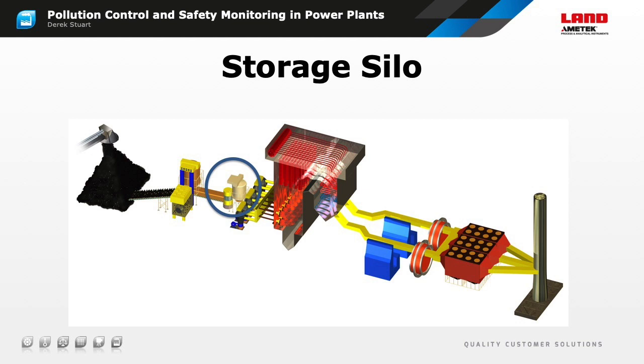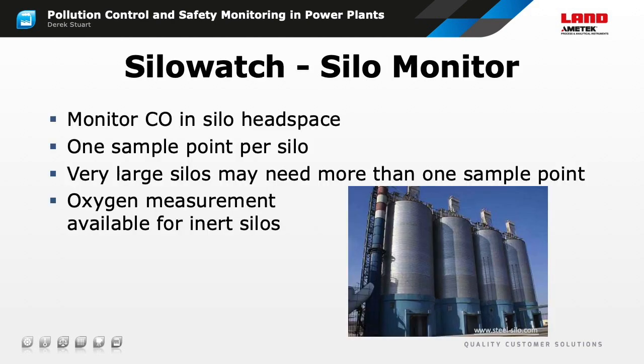Silos are used for short-term storage of fuel close to the boiler. They give protection from the weather and keep the fuel dry. Wet coal reduces combustion efficiency, but enclosed storage is essential for biomass pellets because they will simply disintegrate if they become wet. Because they're enclosed spaces, silos and storage domes are best monitored using a carbon monoxide sensor. The sample point should be located near the top of the silo so it can measure the gas in the headspace above the fuel. In most cases, a single sample point is sufficient because natural convection ensures the gases in the headspace are well mixed.